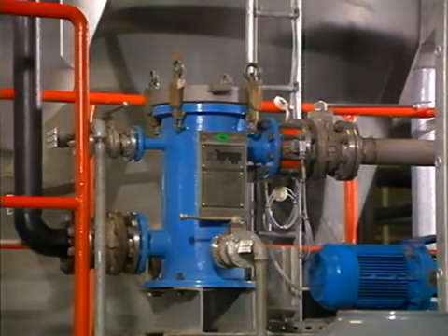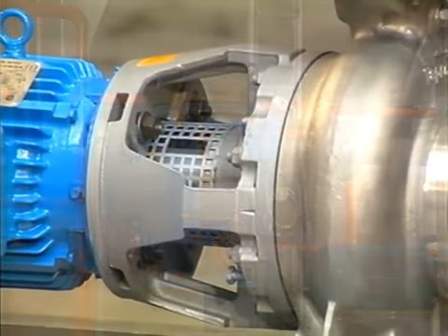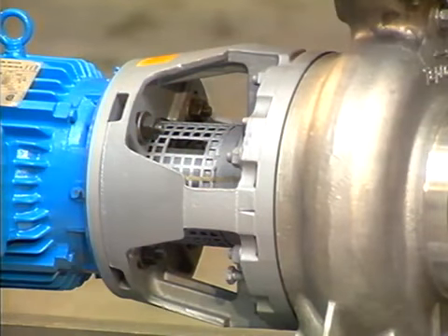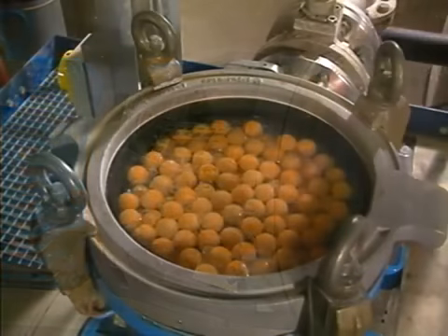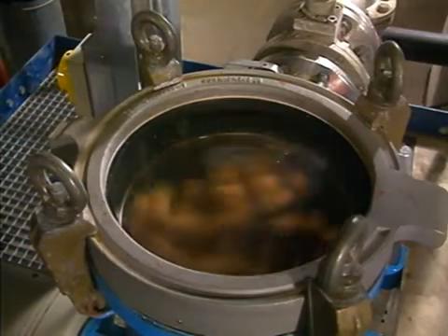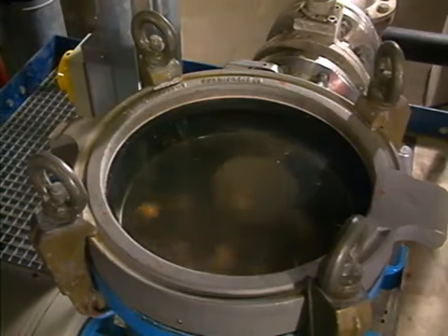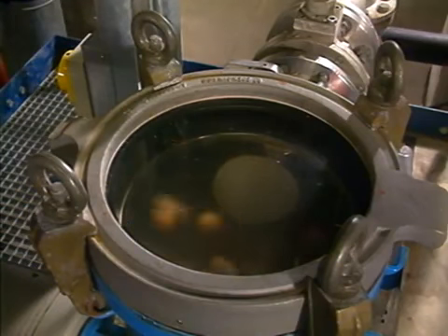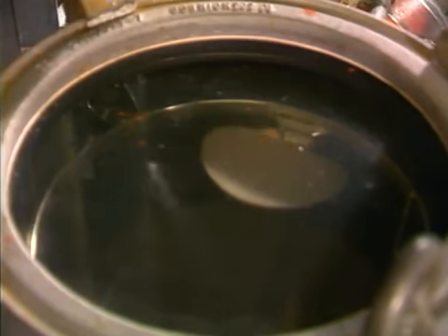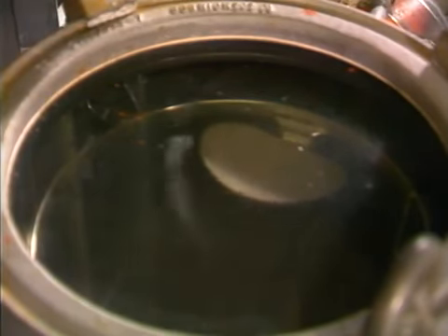This unit consists of a ball recirculating pump and a ball collector. The ball recirculating pump in monoblock design was developed by TAPROGGE together with a leading pump manufacturer to ensure especially careful transportation of the cleaning balls. The ball collector is situated between ball extraction and ball injection, a porthole to view the balls in circulation. The ball collector is equipped with an integral non-return valve to prevent the balls escaping due to reverse flow.